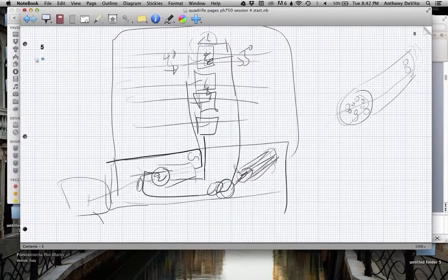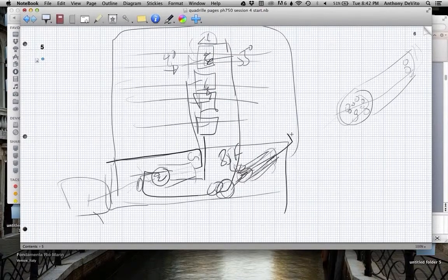You run water over this. The water comes in at about 85 degrees. These are pretty much universal temperatures for these kinds of systems because this equipment is designed to work this way. And the water comes out at 95 degrees. It takes the heat away from the Freon, so it turns it back into a liquid and you can reuse it again, back in your chiller.